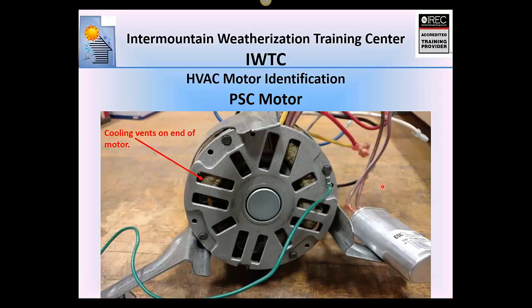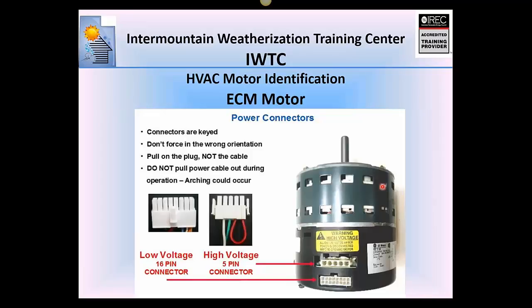ECM motors will almost always have a large 16-pin connector (some older ones have 12-pin), followed by a 5- or 4-pin connector, using Molex plugs. That combination of two big Molex plugs is the most common factory-installed ECM setup you'll see. Retrofit aftermarket ECMs will be discussed separately.